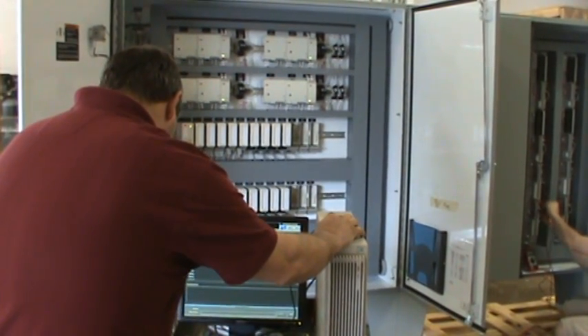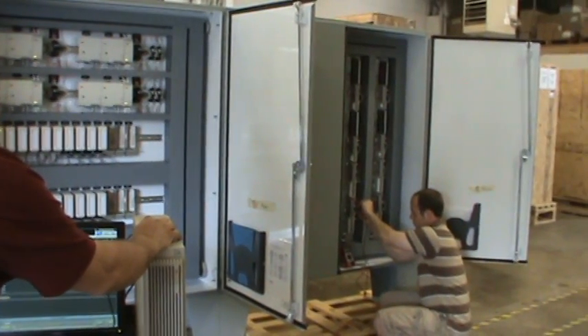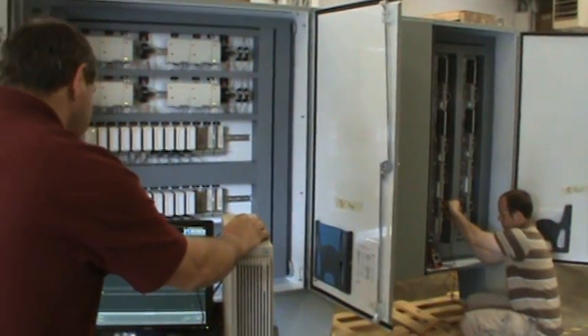In this particular test, Charles is going to turn on a physical output. James will be sitting at the terminal strip with a voltmeter to ensure that we actually have the proper output signal.